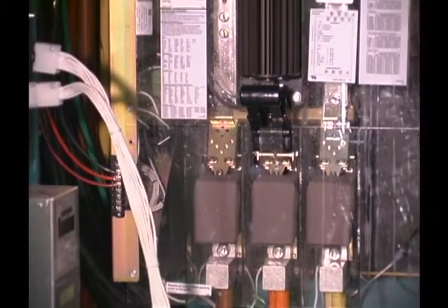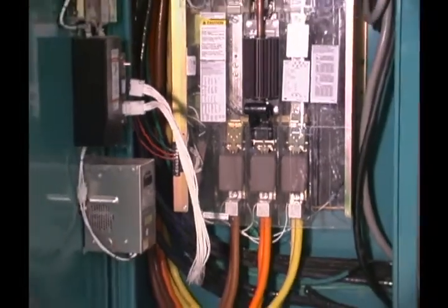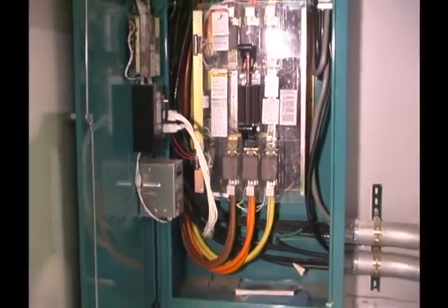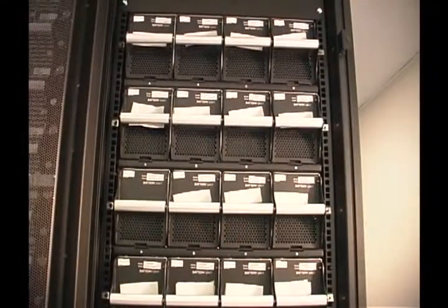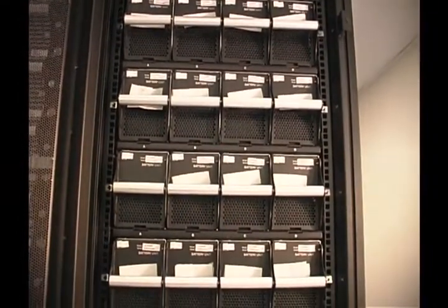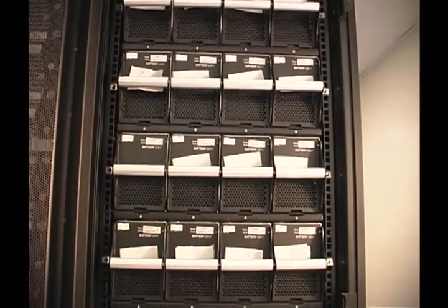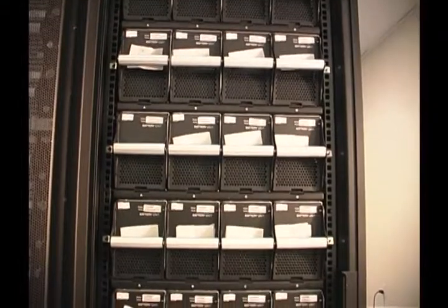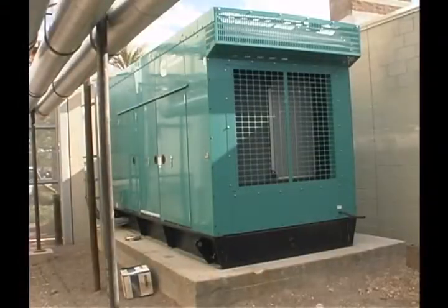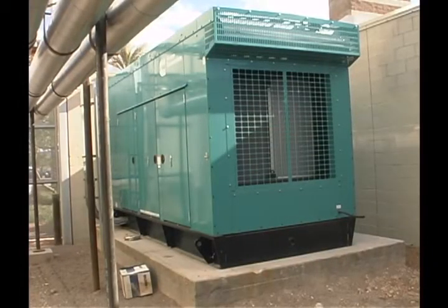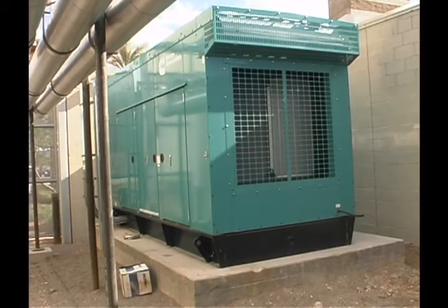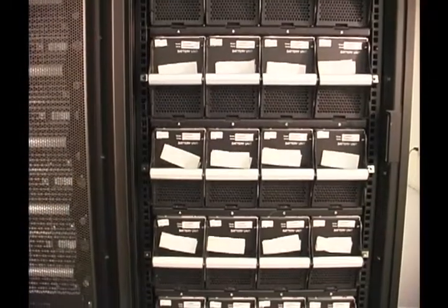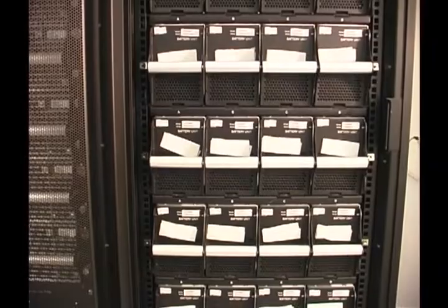The data center is designed with N+1 power redundancy. The entire data center is connected to a backup battery system that can run the data center for 20 minutes in the event of power loss. As soon as a power loss is detected, the diesel generator will automatically turn on to provide power to replace the battery backup. Once power is restored to the data center, the diesel generator will automatically turn off.